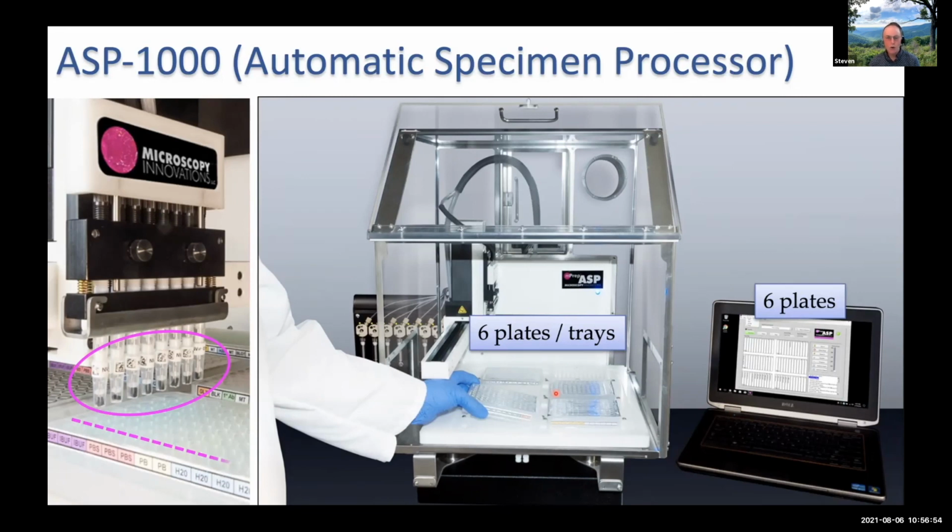And you can organize the plates in any way you desire for a particular preparation protocol. For example, many labs place all the heavy metal reagents in one plate in order to simplify the waste stream handling. And you can even change the plates or add a reagent during a protocol. The ASP can text you when this step is needed, and this enables even more than 72 steps, such as I pointed out earlier, doing pre-embedding immunogold labeling followed by serial block-face TEM preparation.